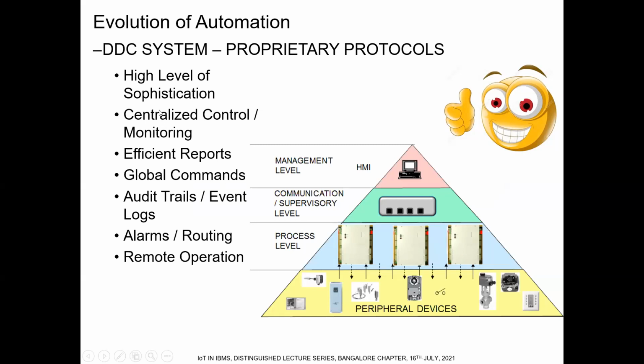Things looked very, very nice at the stage towards the end of last century when these were introduced. You could see here efficient reports, global commands, audit trails, event logs, alarm routing, remote operation. All these were built up into the hierarchy shown here. It looked very nice. And then there was a certain situation. You can see here, these controllers look very much alike. There is a red line connecting these controllers, and then there is a supervisory controller which assimilated data from this level onto the screen here, which was the user interface.